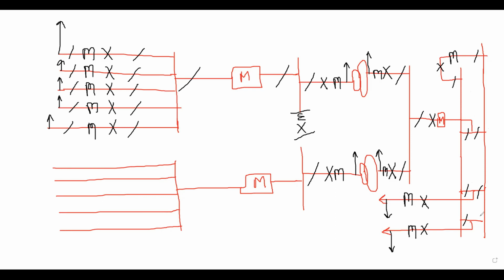Isolators, and line side isolators, because to attend the maintenance again. Right? So again, to discharge the static electricity present in the line, we require earth switches. Earth switches you can place for every isolator, team, because it totally depends upon your requirement. But generally, we will place them on the line side mostly. In the other parts, not required mostly.